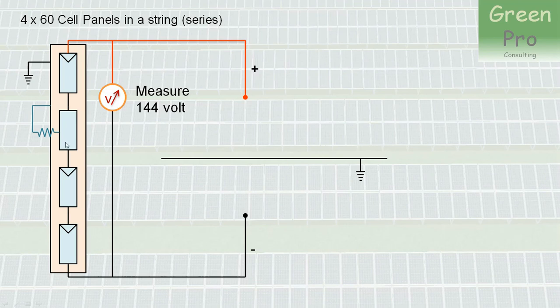So let's look at a string where you do have a problem. I depicted the problem by putting a resistance in there. Now, this isn't a physical resistor that is in there. It is simply my way to depict the problem. And that means that between the inside of the panel and the frame of the panel, you have something which causes a leakage. And that something is a fault. Okay. You could also have a resistance between the wiring there and the frame and earth. Now, earth will probably be the frame. And it should be the frame if you connected this correctly for a transformerless inverter. Again, you make sure that your earth point where you're doing the testing in your inverter room is the same earth as that earth. And now you're going to start doing the same measurement again.